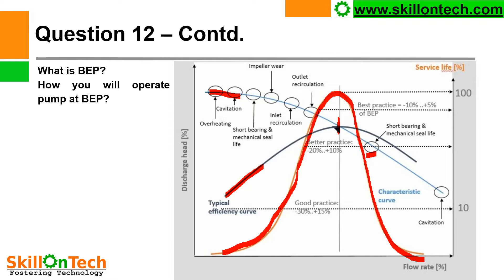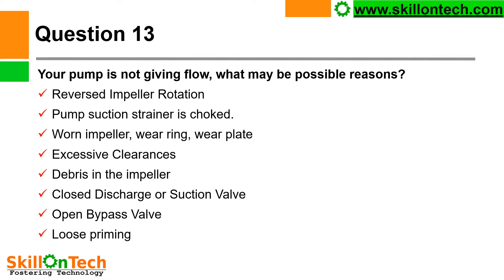Your pump is not giving flow — what are the possible reasons? Let us know one by one. Reverse impeller rotation: if your pump is rotating in the reverse direction, it will not give you flow or discharge. Pump suction strainer choked or clogged.